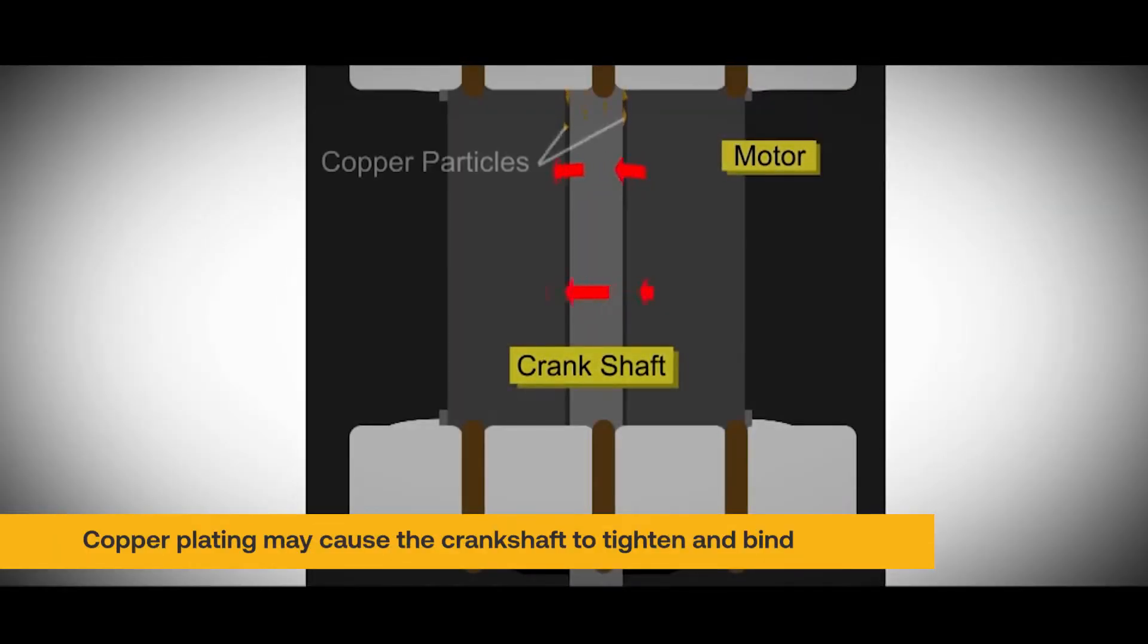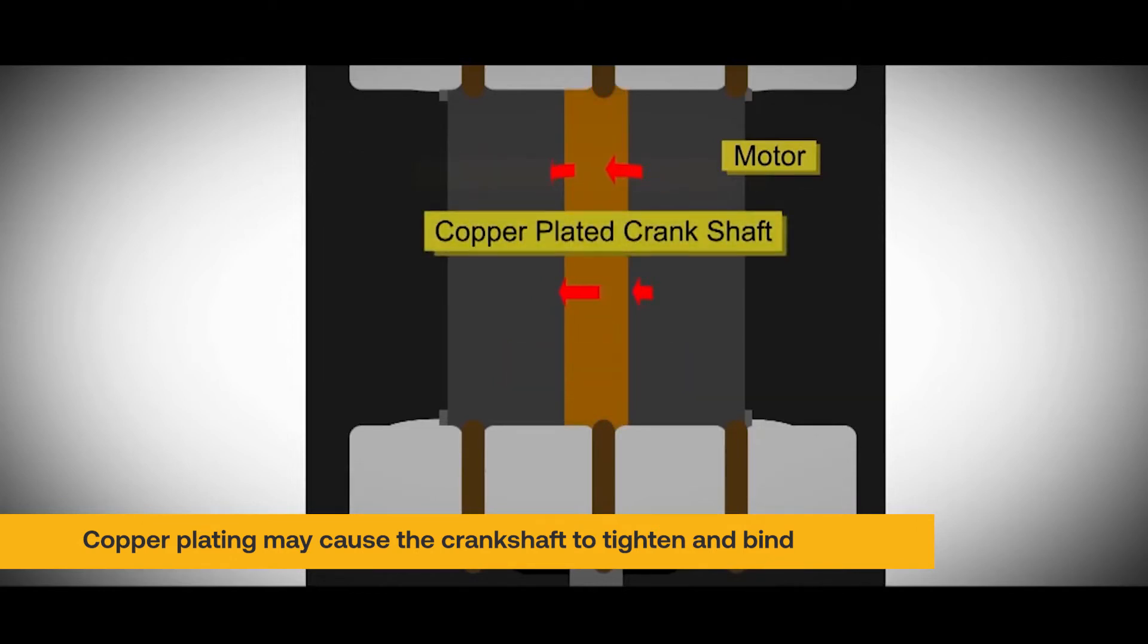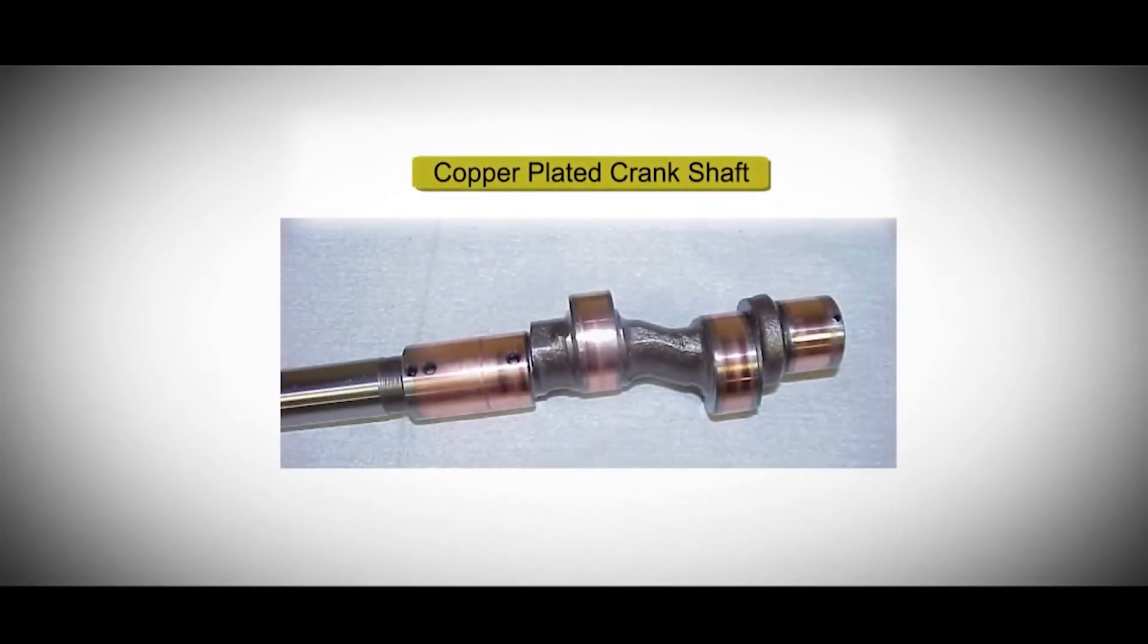Copper particles may reach the crankshaft, one of the hottest points on the system. The resulting copper plating can cause the crankshaft to tighten and bind, introducing the need for hard start kits and leading to compressor failure.